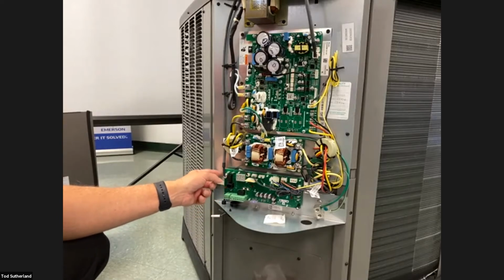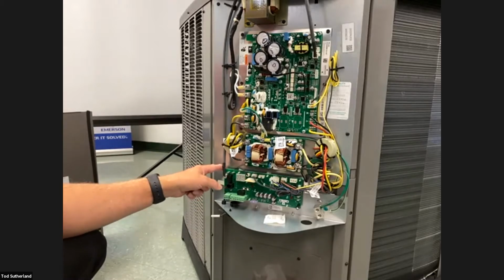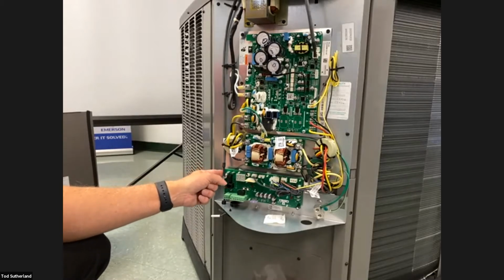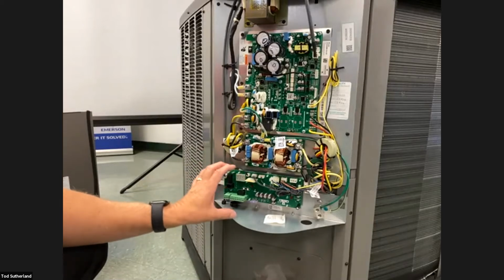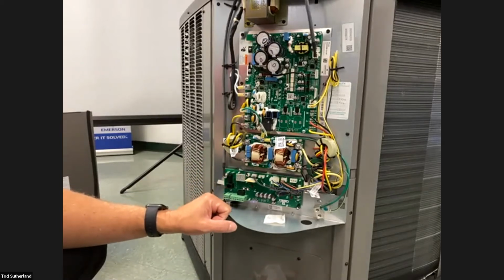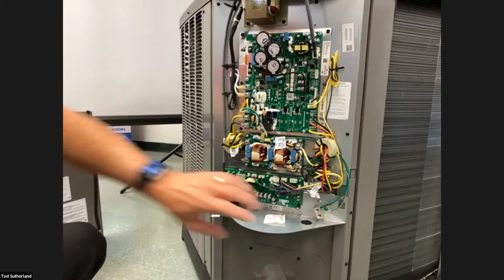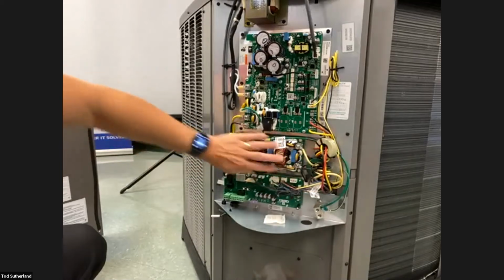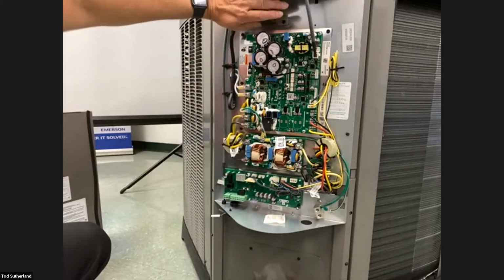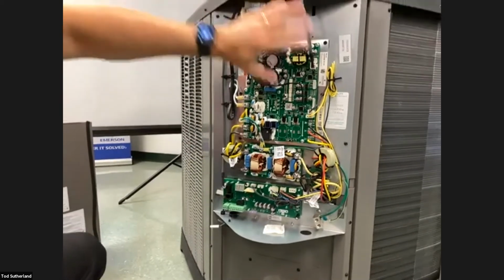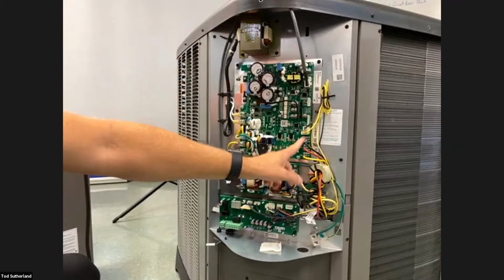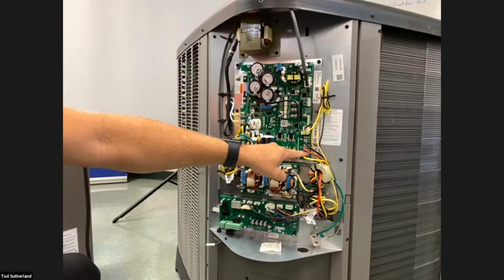This board is a board that they program at the factory to do different things. Some of the early units that came out didn't have as big a tolerance for the brownouts that we have here in Florida. So that's been fixed on the newer boards, where it's got a much greater tolerance to the brownouts that are here. Okay. This is your ferrite rings, your filter board. This all leads up to a choke. This choke all goes into the inverter board. And then this is your voltage that goes out to the compressor.